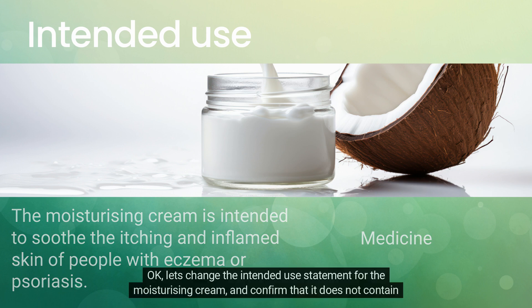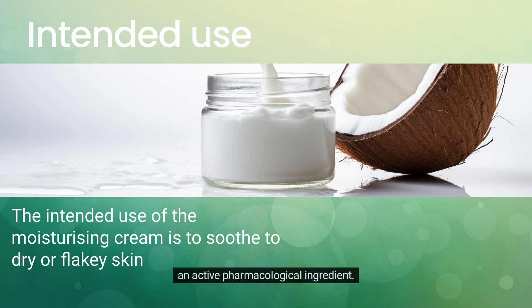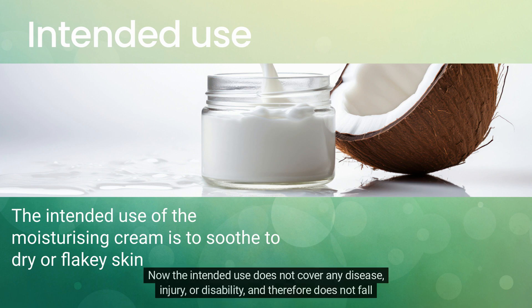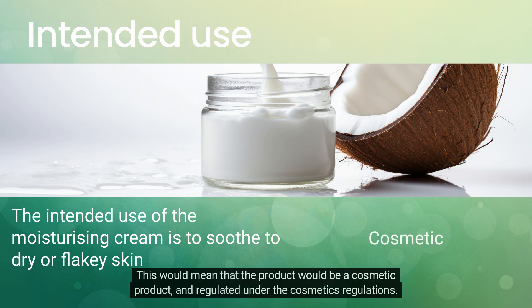Let's change the intended use statement for the moisturizing cream and confirm that it does not contain an active pharmacological ingredient. If the intended use of the moisturizing cream is to soothe dry or flaky skin, the intended use does not cover any disease, injury, or disability, and therefore does not fall within the definition of the medical device regulation. This would mean that the product would be a cosmetic product, regulated under the cosmetics regulations.